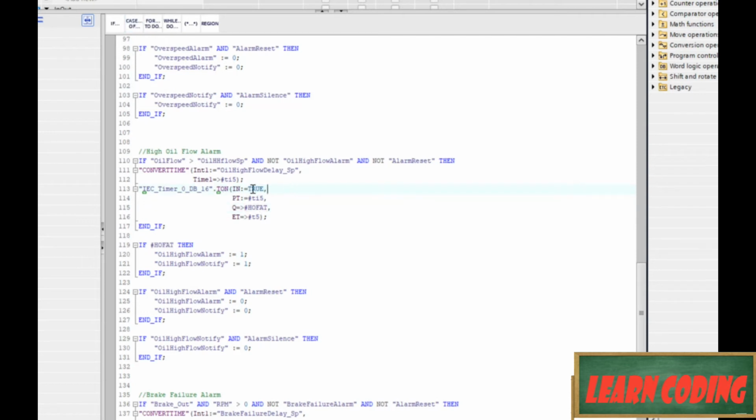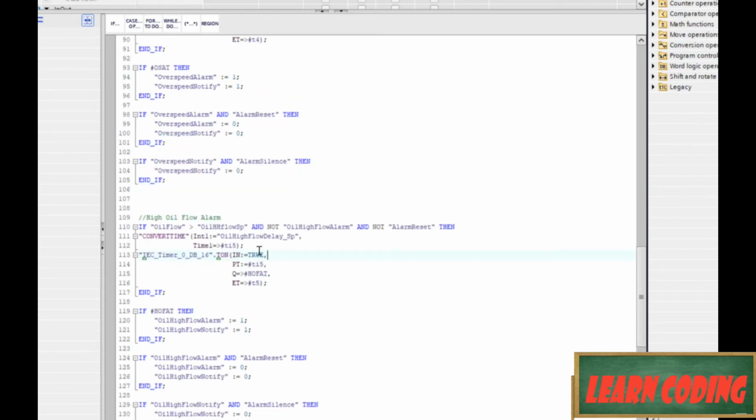So what it looks like is happening is, because I've got this true value in the timer, that timer is loading its value. Anytime we come into this if block, it's considering itself true, and there's never a reset. Okay, so what we're going to do here is just reset that timer. So let's come over here to timers, and you see here we've got this reset timer function, right?